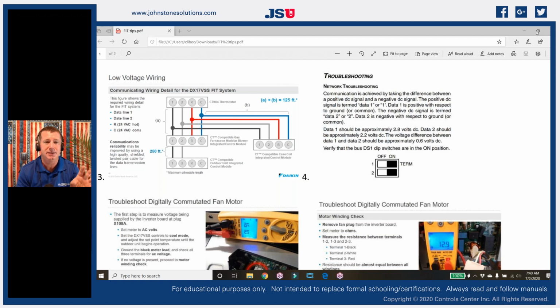they're very polarity sensitive. So we have to have all the number 1s connected to number 1s and all the number 2s connected to number 2s. Because what we're doing is taking that 5-volt DC signal and breaking it up into a positive signal and a negative signal. If you take your meter and you're testing communicating networks using 5-volt DC, you can put your negative or black terminal on ground or common, because the common side of our transformer should be grounded. Go from common to number 1, and you're actually going to see a positive DC signal.